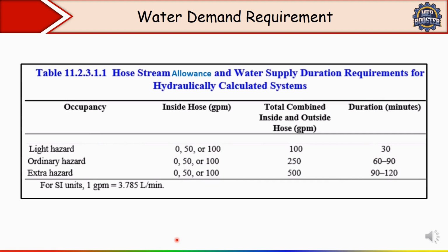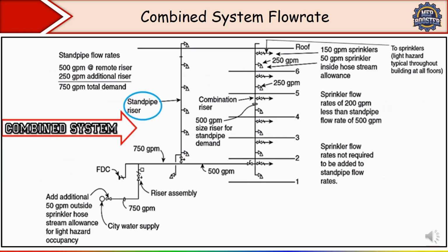Okay, and depending on the building fire protection strategy, an inside hose allowance might be set as 0, 50 or 100 GPM. Okay, so now let's see the example which we have discussed. Here you can see one example is shown for light hazard occupancy. Here it is written: light hazard typically throughout building at all floors. Okay, so the diagram illustrates the flow rate distribution for a combined sprinkler and standpipe system. So let us analyze each part in detail.